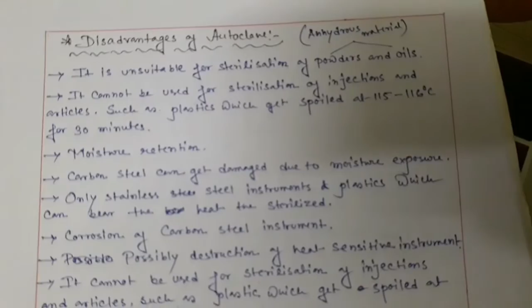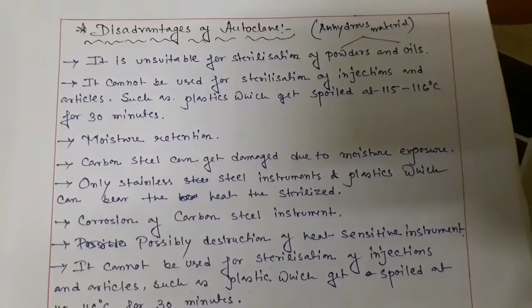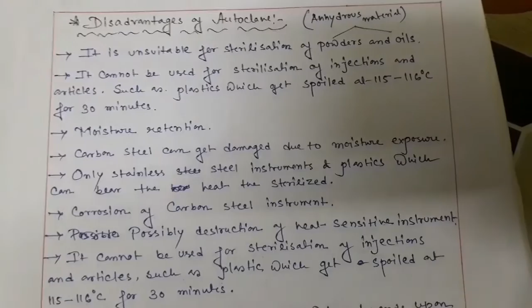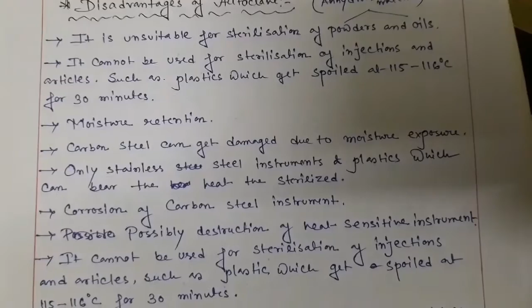It is unsuitable for sterilization of powders and oils. They are called anhydrous materials. That means it is not suitable for anhydrous material, and it cannot be used for sterilization of injections and articles such as plastic, which gets spoiled at 115 to 116 degrees centigrade for 30 minutes. This type of condition is not suitable for the autoclave. And with moisture retention, carbon steel can get damaged due to moisture exposure.